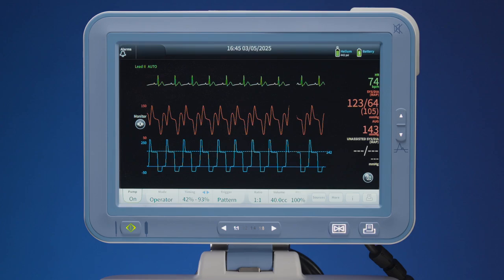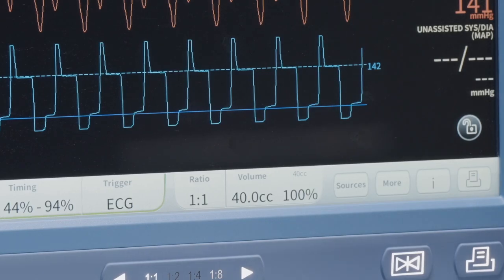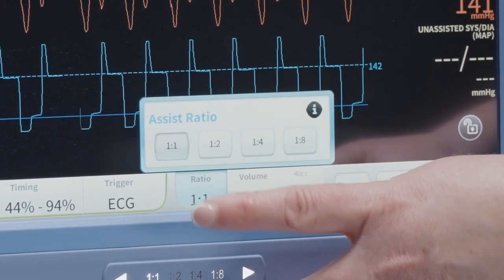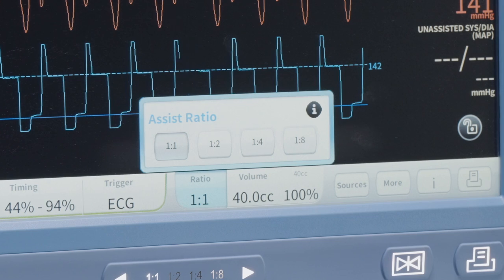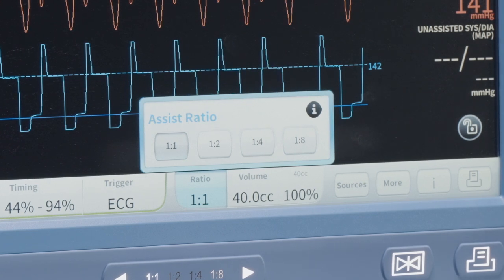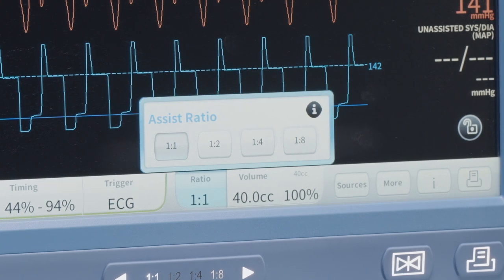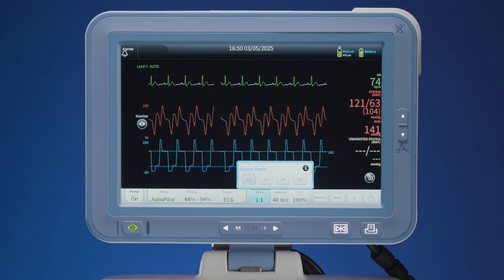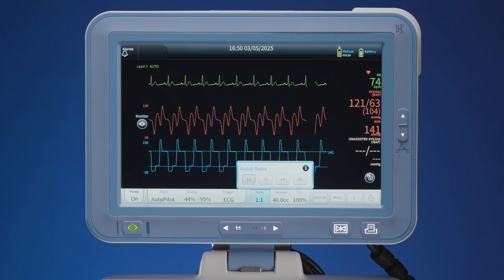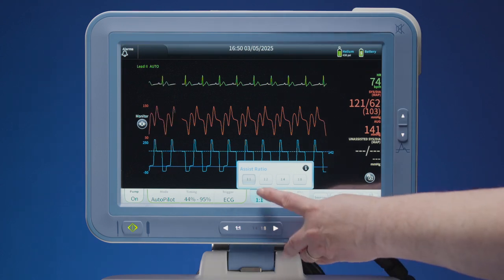The assist ratio touchscreen key allows the user to select the frequency of IABP assist the patient will receive. The function is active for both autopilot mode and operator mode. The default assist ratio is 1:1 on startup of pumping. The user can now select the desired assist ratio.